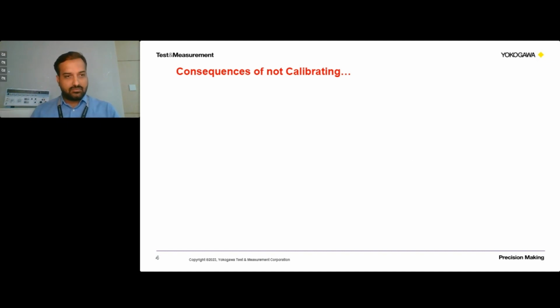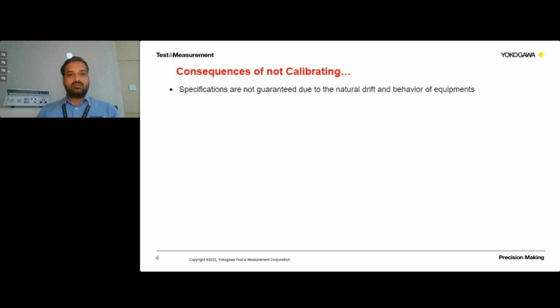Next, we'll discuss what are the consequences of not calibrating. So what will happen if the test and measurement instruments are not calibrated on time? Specifications are not guaranteed due to the natural drift and behavior of the equipment. That means when we do not calibrate our test and measurement instruments on time, the defined specifications will not be guaranteed. So we may have results which are out of specifications and which may not give the desired results.